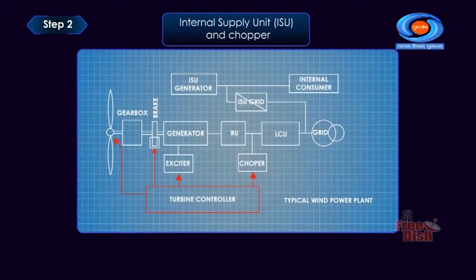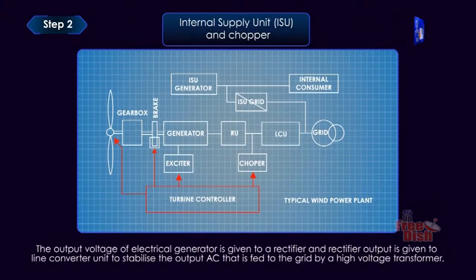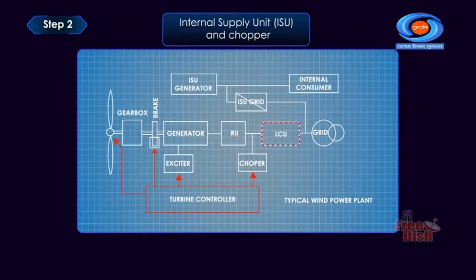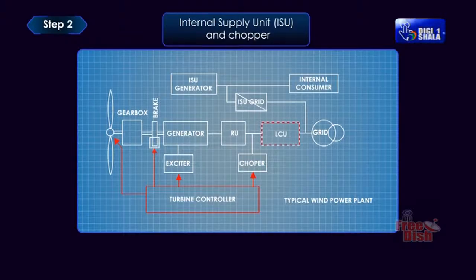Internal Supply Unit (ISU) and Chopper. The output voltage of the electrical generator is given to a rectifier, and the rectifier output is given to the line converter unit to stabilize the output AC that is fed to the grid by a high voltage transformer. An extra unit is used to give power to internal auxiliaries of the wind turbine like motor, battery, etc. This is called the internal supply unit. The ISU can take power from the grid as well as from wind. The chopper is used to dissipate extra energy from the rectifier unit RU for safety purposes.